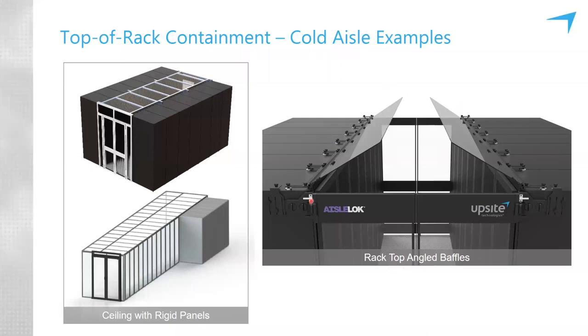On the right here is an example of rack top baffles, and rack top baffles are a very useful way to get into the containment world at a relatively low cost and a very simple solution. Each of these is modular. There's one baffle on top of each cabinet and they attach magnetically. So this whole aisle can be deployed in just a few minutes. And what these do is they prevent hot air from rolling into the aisle and they contain the cold air that's here slightly, but they don't block gaseous fire suppression. And in most cases, the AHJ fire marshal doesn't have an objection to these, and the sprinkler is still an acceptable solution for fire suppression. So these can be a really good option for improving airflow management without going to full containment.